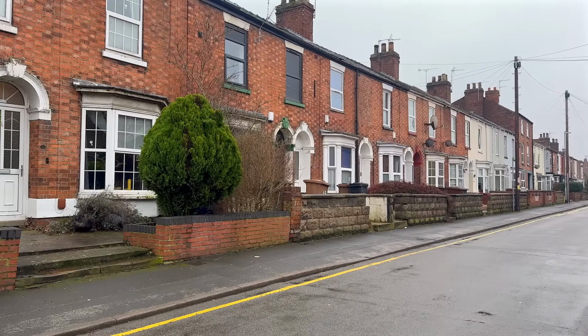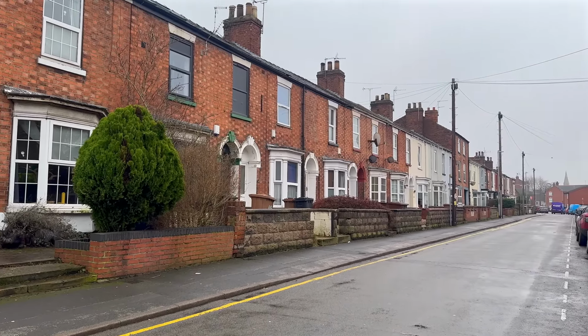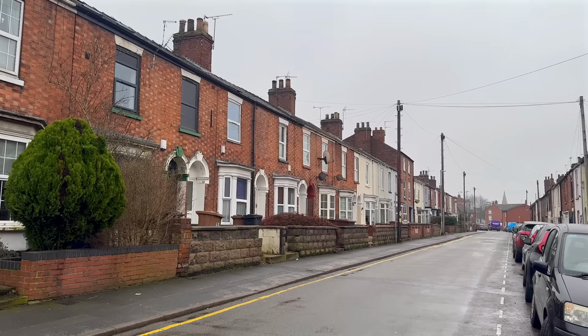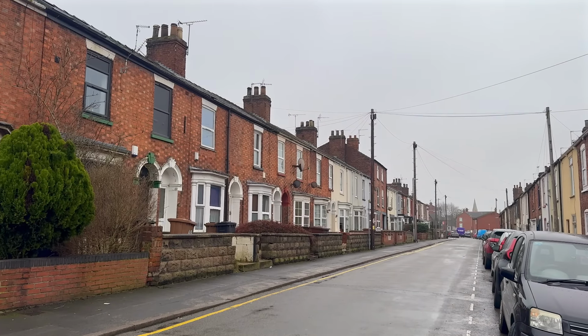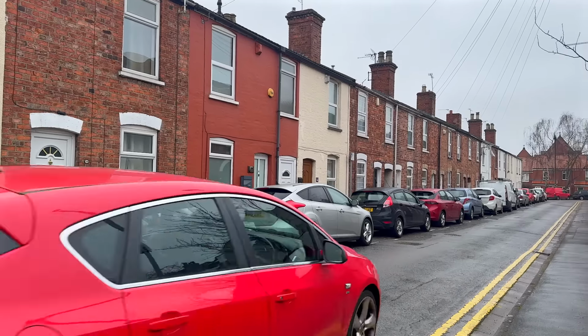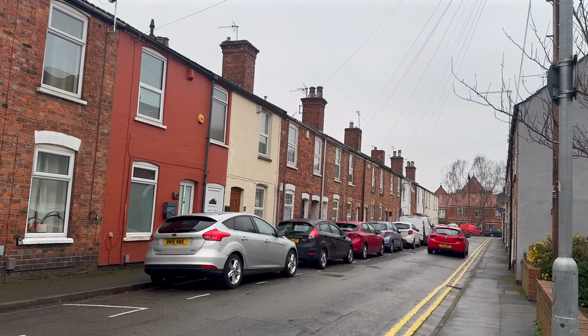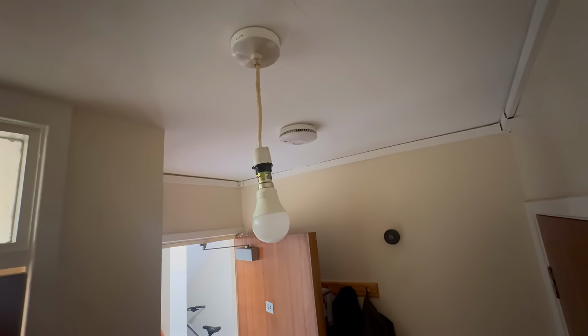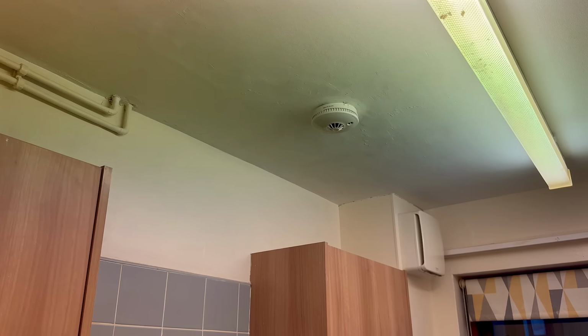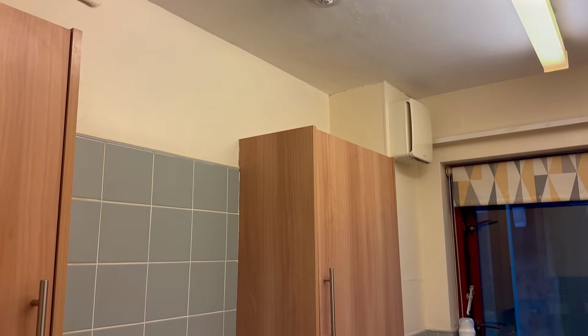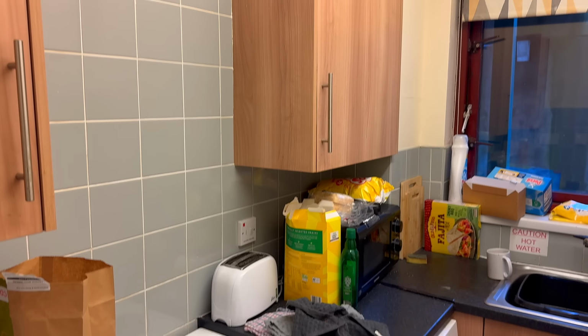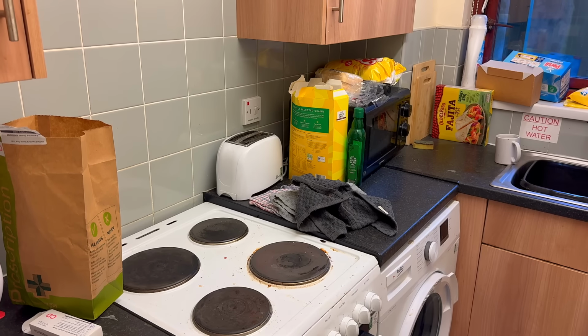The individual letting accommodation might be a bedsit, a single room with or without cooking facilities, or a letting unit made up of 2 or more rooms. Although these sit within a larger shared building, the fire detection inside these units is still based on domestic principles. For these areas, the guide points towards a grade D1 system. That means mains powered alarms with a sealed, tamper-resistant backup battery installed to provide reliable warning within the space that the occupant lives and sleeps in.